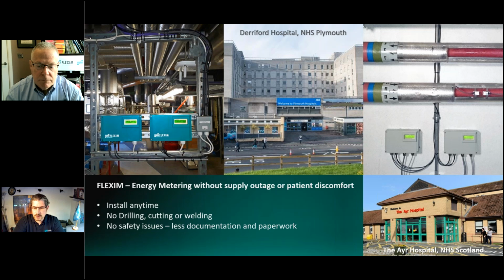Nobody will even notice that you have installed an energy meter, because you just clamp the transducers onto the pipe. The same goes for the temperature probes. So there is no drilling, cutting, or welding, and also no safety issues. You do not have to take care of fire safety if someone starts welding in any place in your estates. So this also improves the safety of your systems.